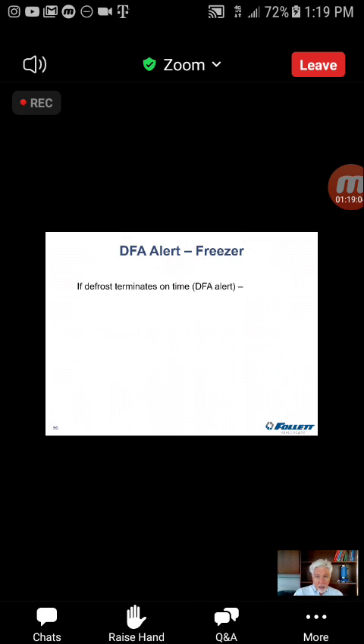If we terminate on time, okay, what do we want to do? First thing we want to do is check to make sure that the defrost heater is working. And in some of our manuals, we have the specification on this. I know we can get it from tech support. I haven't bothered to memorize it because the nice thing about defrost heaters, they're either good or they're bad. If it's drawing current, it's safe to assume the heater is doing what it's supposed to be doing. But if you want to verify, like I said, those numbers are available from tech support.